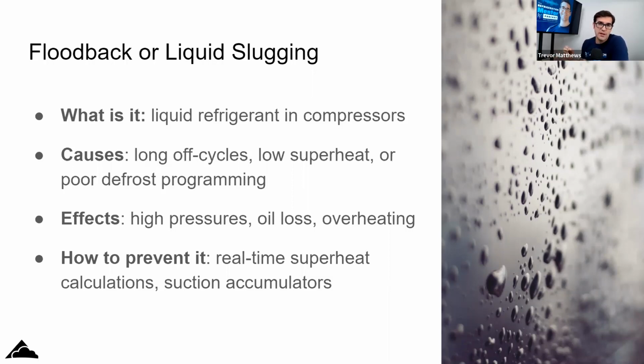So checking your system superheat, you can call it compressor superheat as well, knowing exactly what's happening to that compressor. You get discharge superheat as well, to tell if liquid is condensing inside the compressor. So there are so many different analytics you can do. It's happening now, especially on the newer systems, like I said, in CO2 refrigeration. On the older systems, some people are starting to add more of these sensors, like for airflow. There's a big one, people.